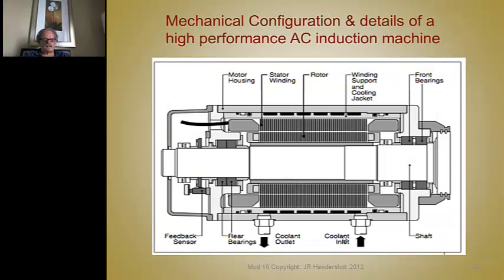Here's a cross-section of a very high-performance induction machine that's used in things like machine tool spindles. You see that you have your rotor core and your stator core. Here's your die-cast rotor end rings, and the conductors go all the way down through here. And this one happens to have a liquid cooling jacket around the outside. It's sealed, and you bring liquid coolant in here, and it goes around these spiral grooves in the OD and exits the other end.